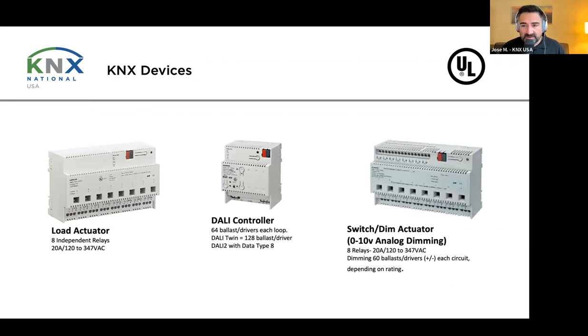Let me show you some examples of KNX devices so you have an idea of what we're talking about. First, we have a load actuator - an on-off actuator to control up to eight loads per channel, for example. This is dual certified, it's in the market in the US, available and certified, and can be used for commercial or residential. This one is from Siemens, and you have up to 20 amperes, which is mandatory for commercial buildings.